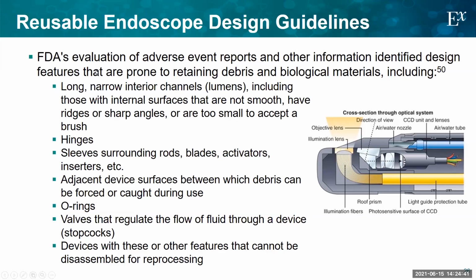So the FDA looked at all these adverse event reports and information about designs and tried to figure out, well, where are the bacteria hiding on these devices? And predictably, they said, well, it's clearly a risk to have long, narrow channels, especially with sharp edges or rough surfaces. Any sort of hinge, sleeve, any gaps between different parts, O-rings are a great place to trap bacteria, valves, and any structure like this that you can't easily take apart for cleaning is going to be a problem. And so that should be avoided in a design of this type.